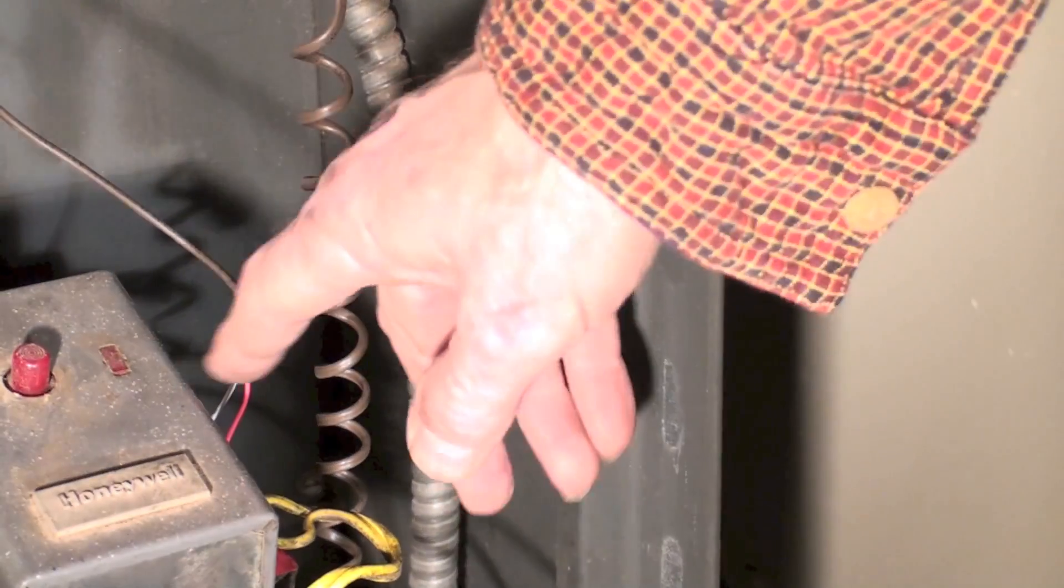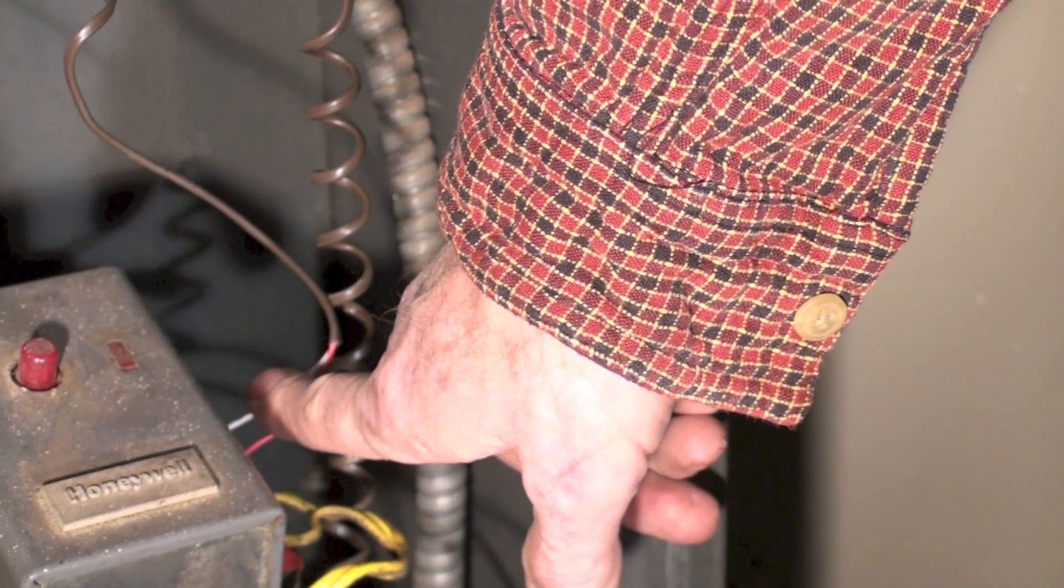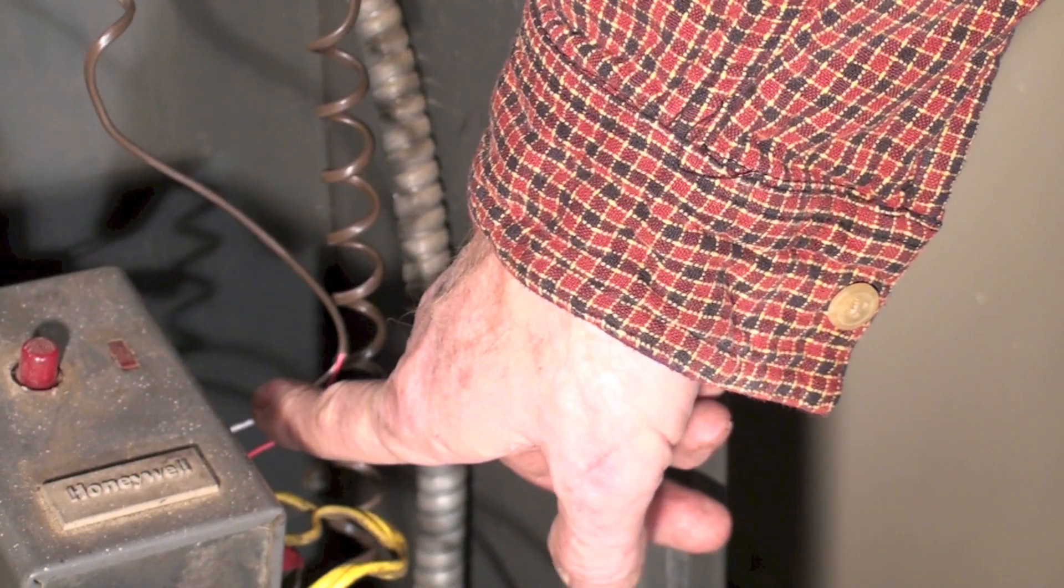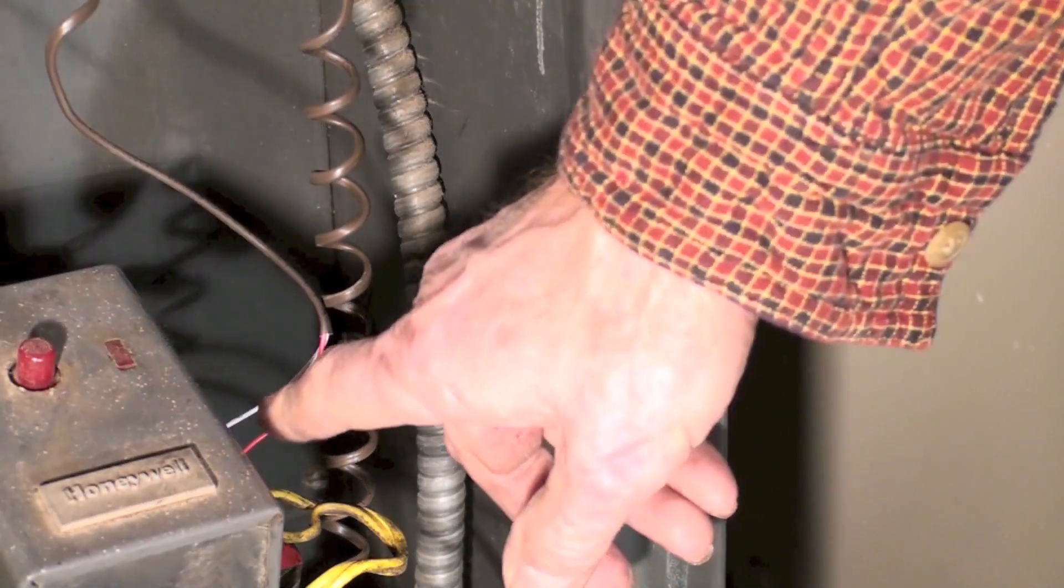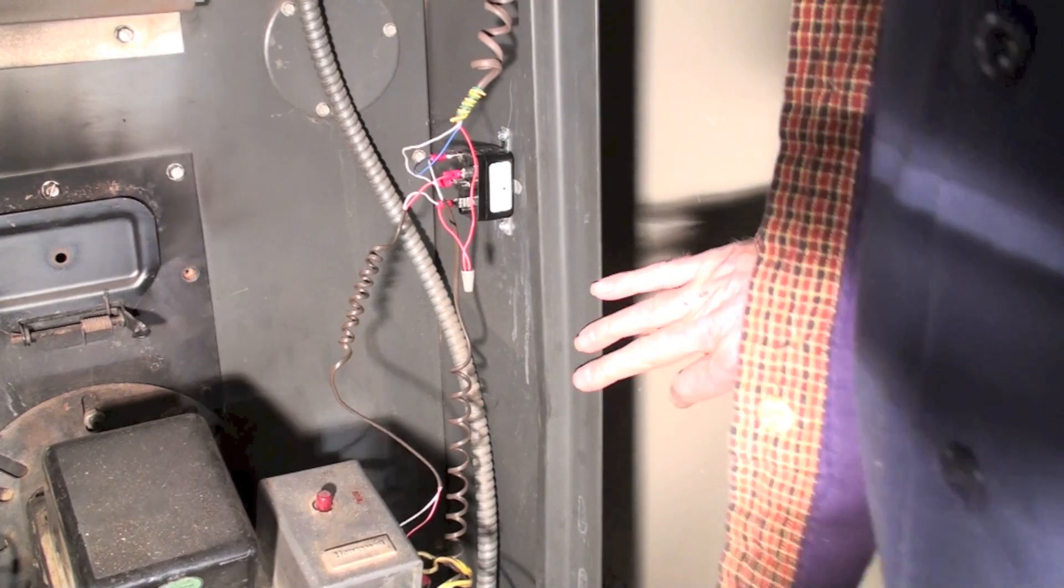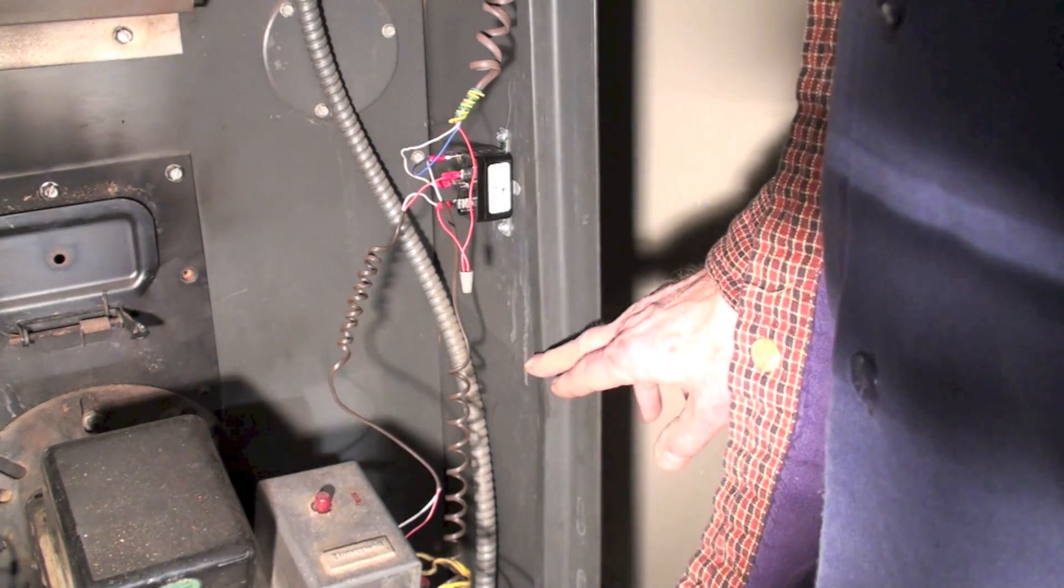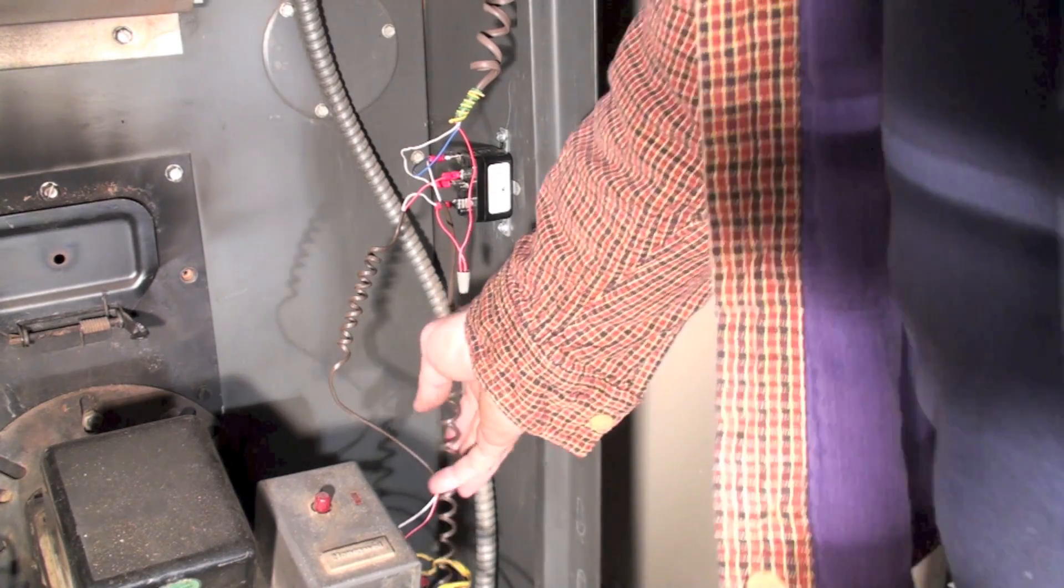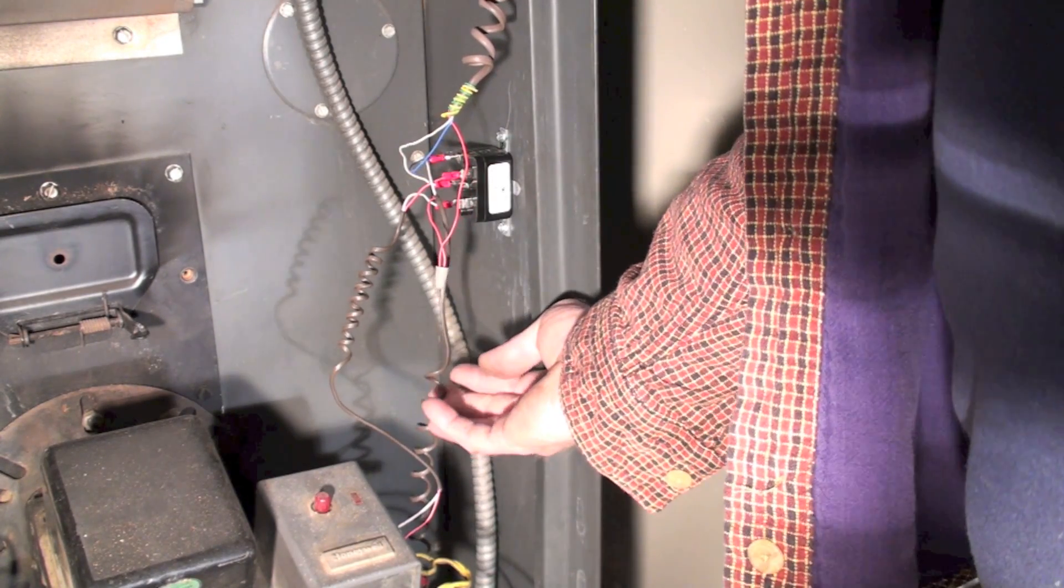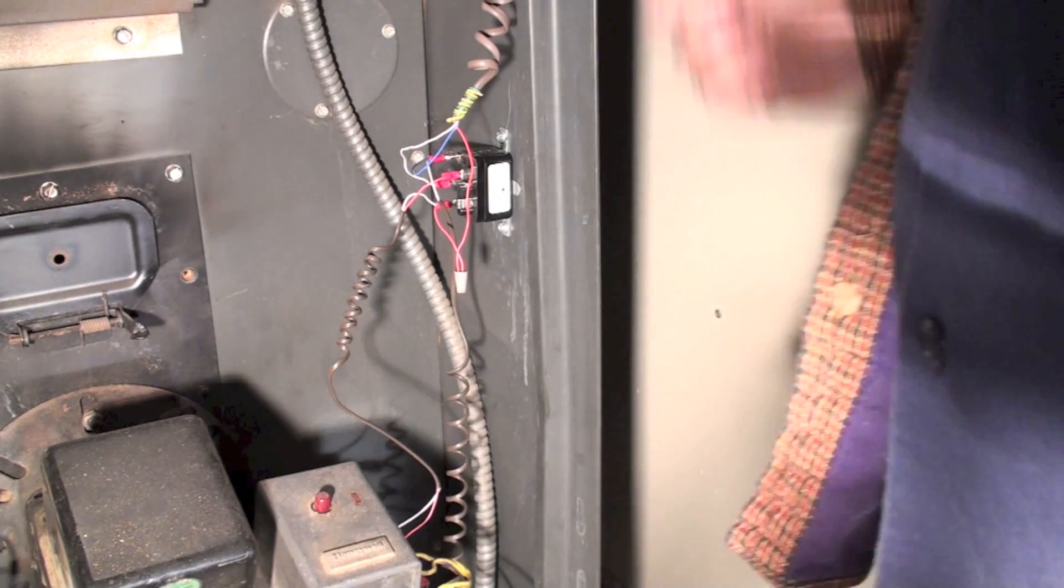When the relay energizes, that closes between two and four on this relay, which goes down to the TT terminals on the cad cell relay. So this completely isolates the cad cell relay, which is down here, from the transformer.